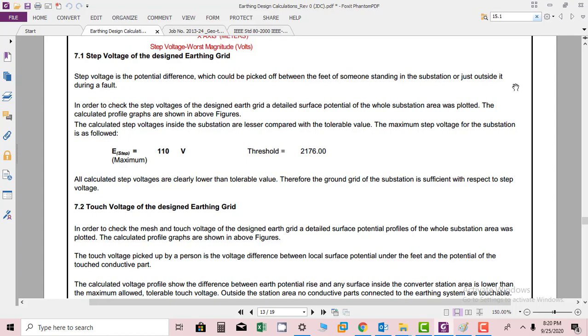In order to check the step voltages of the designed earth grid, a detailed surface potential of the whole substation area was plotted. The calculated profile graphs are shown in the figure that we have already discussed.